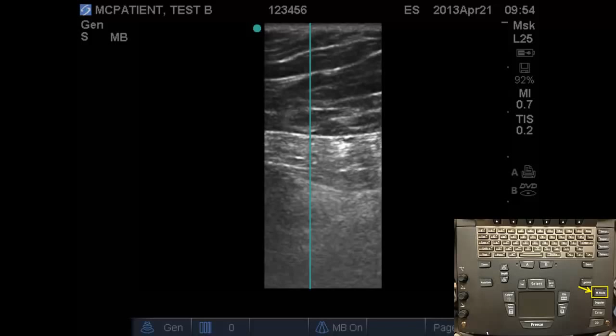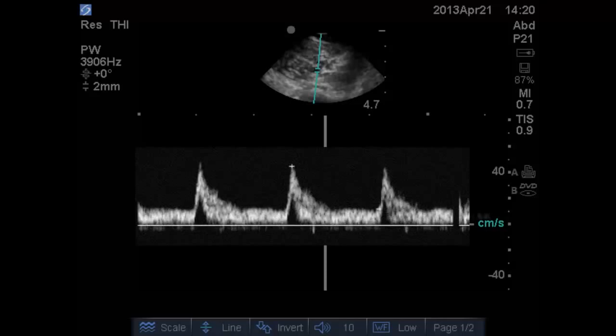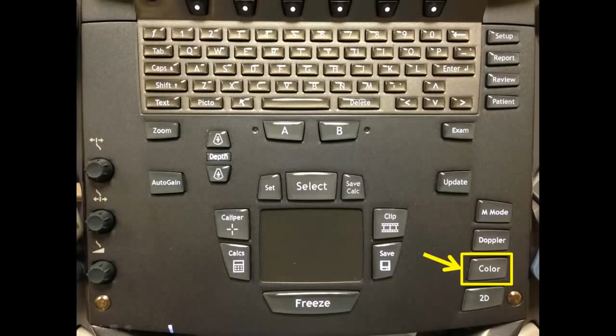D, or Doppler mode, may be used to measure velocities across areas of the screen. Press the Doppler key once to bring up the sampling gate and highlight the area of interest with the trackpad, similar to how M mode was set up. Once you have your area targeted, press the Doppler key again to bring up the spectral tracing, which displays velocity of flow on the y-axis. C, or color Doppler mode, may be used to visually identify flow using color overlaid on top of the B mode image. Press the color key once to bring up the ROI, or region of interest box on the screen.